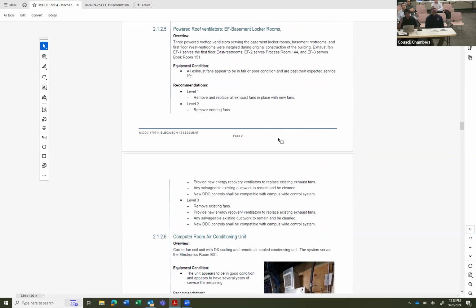And moving on to the powered roof ventilators, the exhaust fans. In the building, there are 3 powered rooftop ventilators serving the locker rooms, restrooms, and first floor restrooms and west restrooms, and they appear to be original to the building, and they effectively are doing the expected job. But I would recommend replacement just based on the age for the level 1 option. Level 2 option, the exhaust fans would be removed, and we'd replace the fans with the energy recovery ventilator. So the energy in the outgoing exhaust air would go through a heat exchanger, and that energy would be exchanged with the incoming outside air to feed the system.